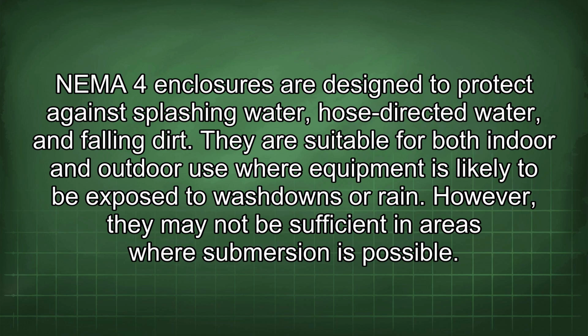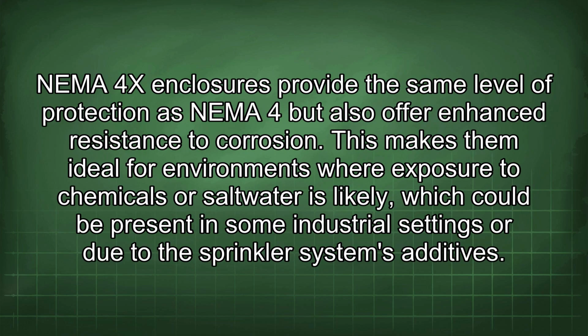They are suitable for both indoor and outdoor use where equipment is likely to be exposed to washdowns or rain. However, they may not be sufficient in areas where submersion is possible. NEMA 4X enclosures provide the same level of protection as NEMA 4 but also offer enhanced resistance to corrosion. This makes them ideal for environments where exposure to chemicals or saltwater is likely, which could be present in some industrial settings or due to the sprinkler system's additives.